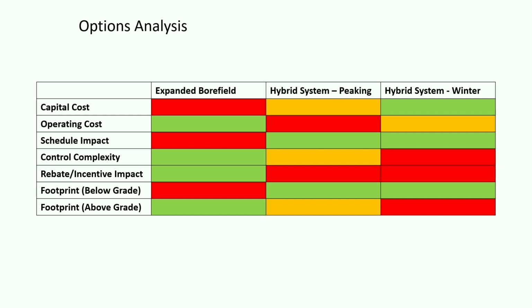I will say a dry cooler tends to be much more complex to control and install because you have to be aware of what your outside temperatures are versus your loop temperatures. You obviously cannot cool your loop and cool your system if it's warmer outside than your condenser water is.